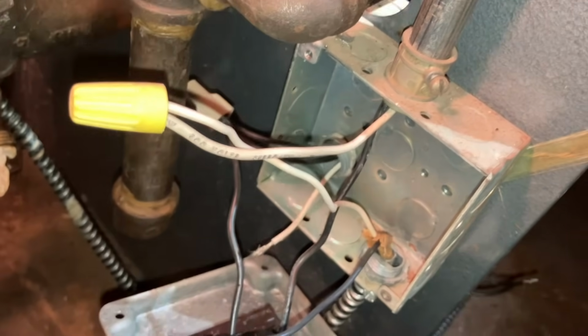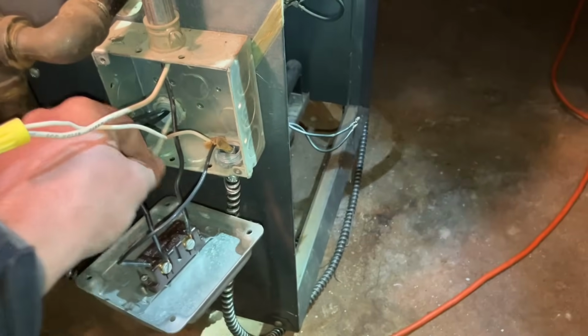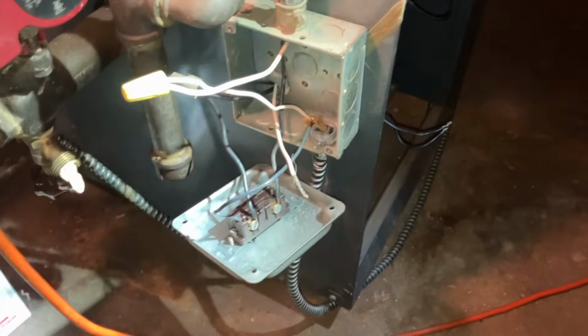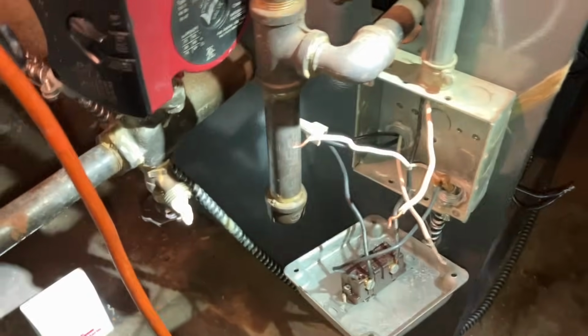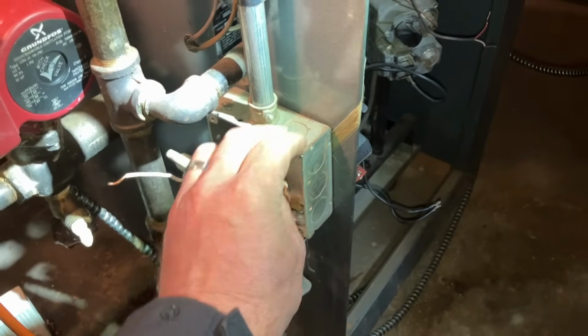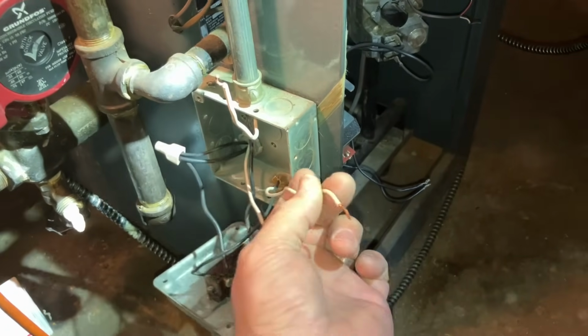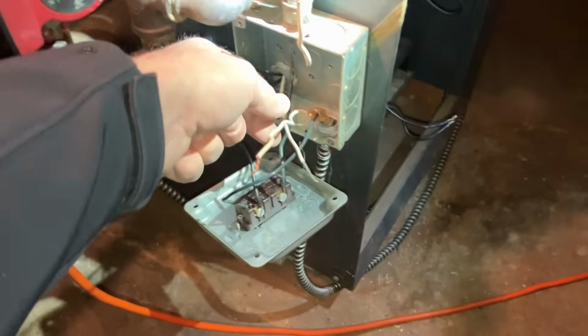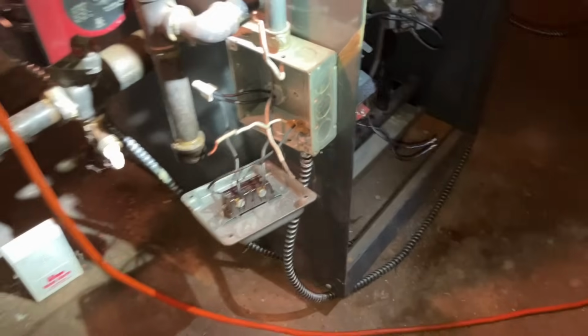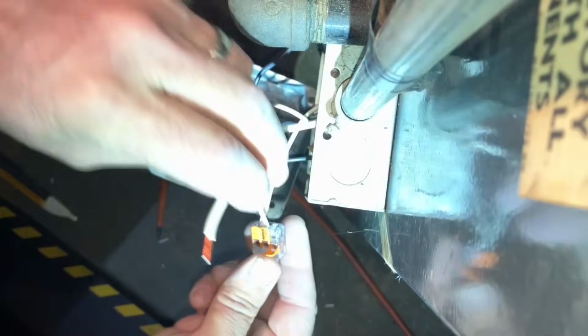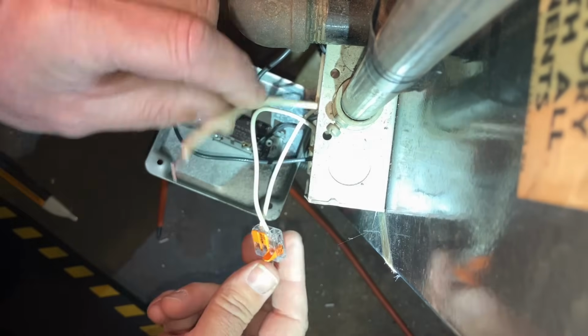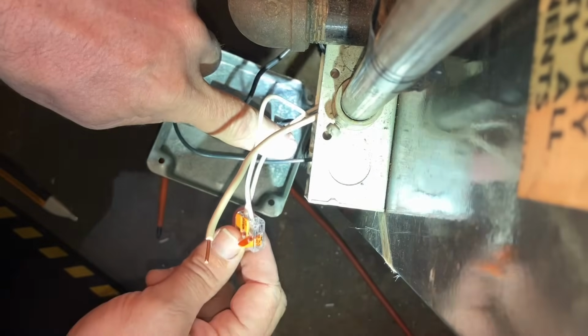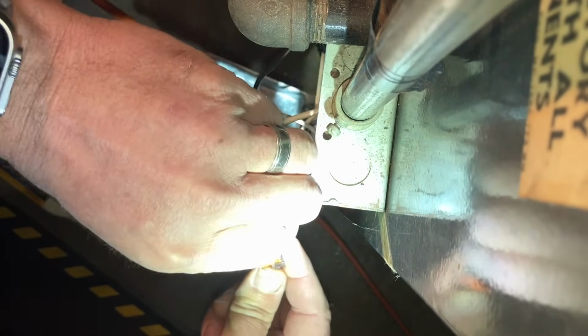But our neutral, and the white should be the neutral, right? Yep, our neutral. Let's get that neutral in there without causing any other problems. Okay, so there's our neutral. Now what we're going to do is, this is our line neutral. This is our neutral going to the switching relay. And here's the neutral going to our transformer. So we need to connect those 3 together and pray for the best. All right, so I have that neutral coming from line, neutral going to our relay, and neutral going to our transformer. So all those are in there now.